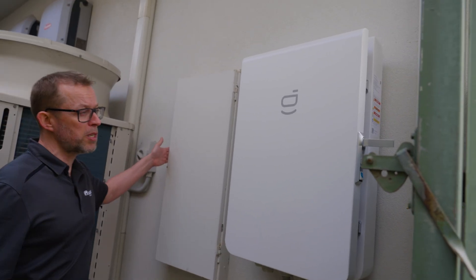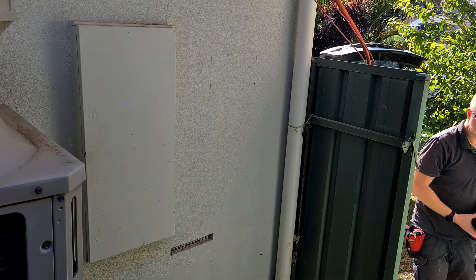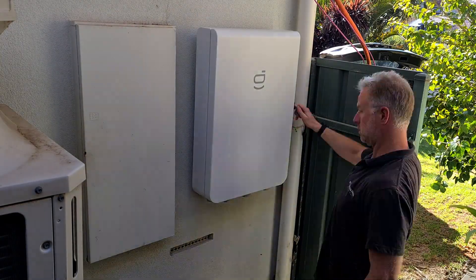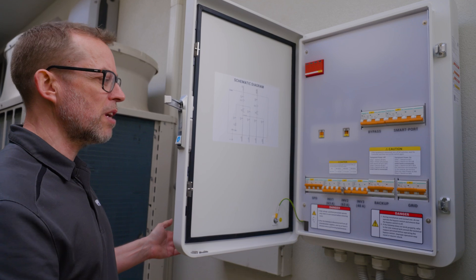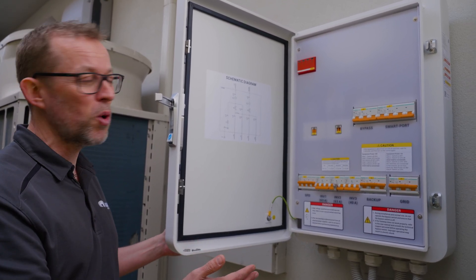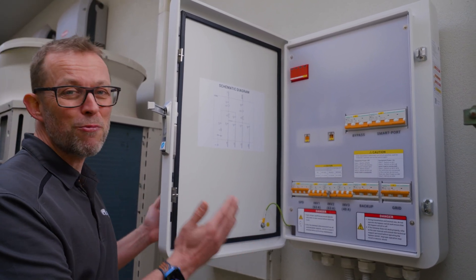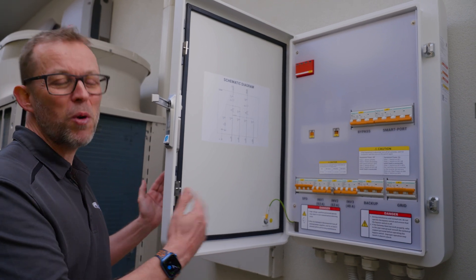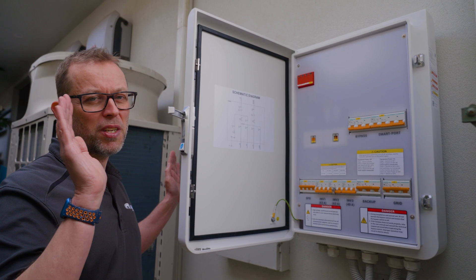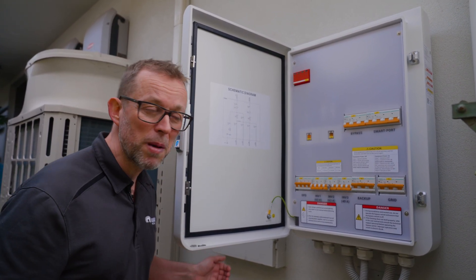This is the house switchboard and this is the gateway. The gateway is used for backup — the whole battery stack can back up the whole house, and the gateway handles all the wiring and the switchover. When the grid goes down, you get uninterrupted backup. That uninterrupted part is really important because it's pure UPS, meaning the switchover time rounds down to 0 milliseconds. So no matter what sensitive equipment you've got running, when it goes into backup mode nothing shuts down and nothing gets corrupted.